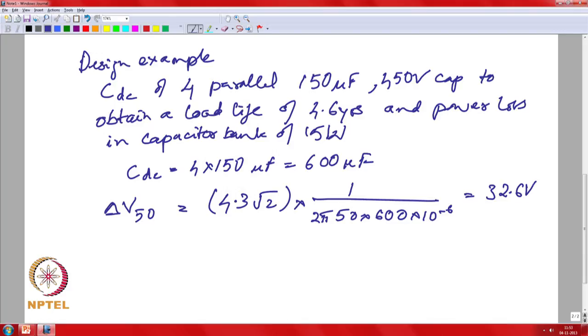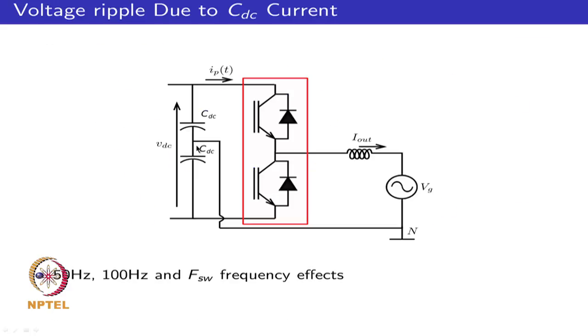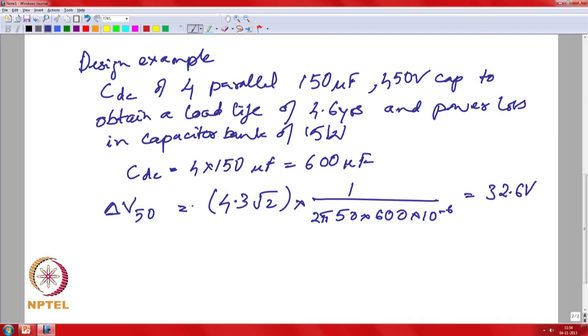We can observe that this 50 Hz effect applies such that if the current is positive, it charges up the bottom bank and discharges the top bank. So you might have +33 volts on one bank at one instant but the top bank will have −33 V. The total voltage across the entire bank is not affected by this 50 Hz — on a total bank basis it is not observed; it is not seen on VDC.